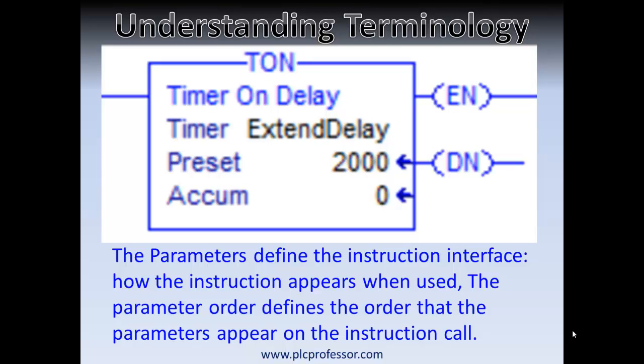If you look at this instruction — this is an on-delay timer — the function of parameters will become clear before long. Parameters are the data ports into and out of an add-on instruction. If you think of parameters in terms of an instruction you're already familiar with, like this TON on-delay timer instruction, it may help place this into context. Now look at the TON instruction — how many parameters do you see? There are actually four visible and a fifth that is usable but not on display. The timer field, or the name of the timer, is not a parameter.